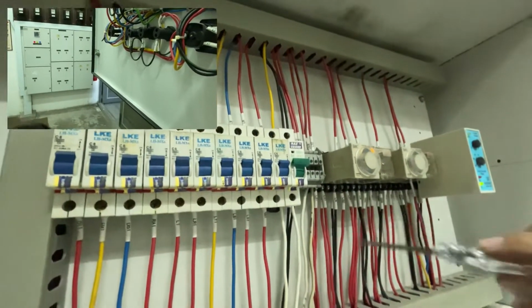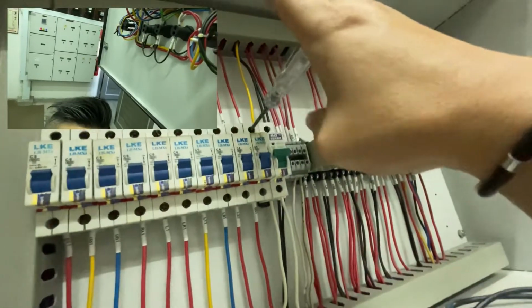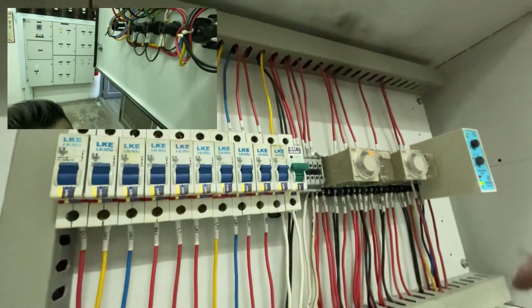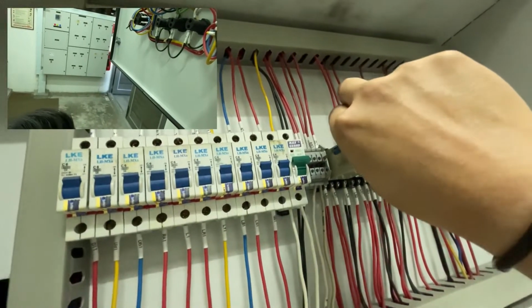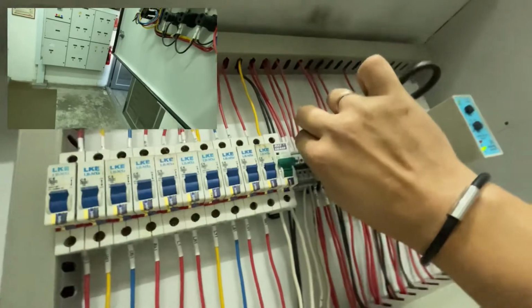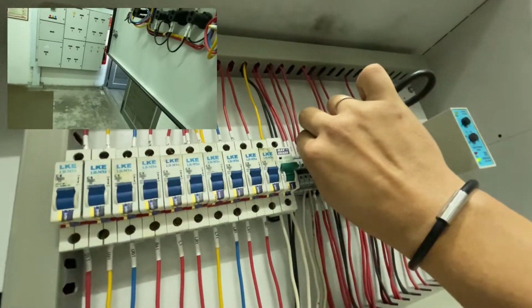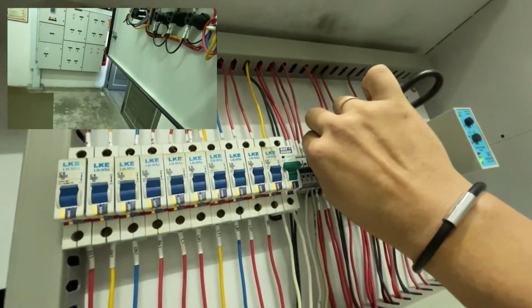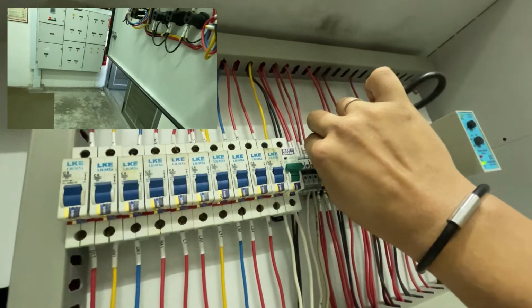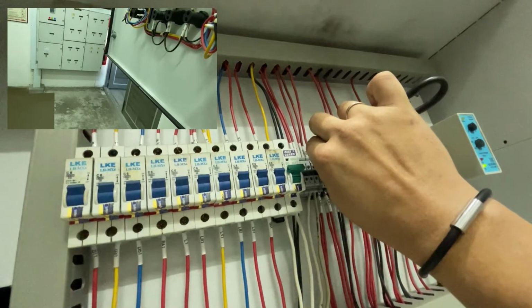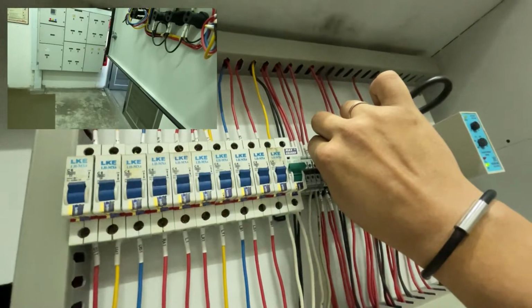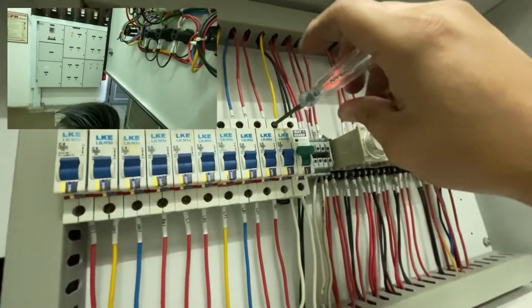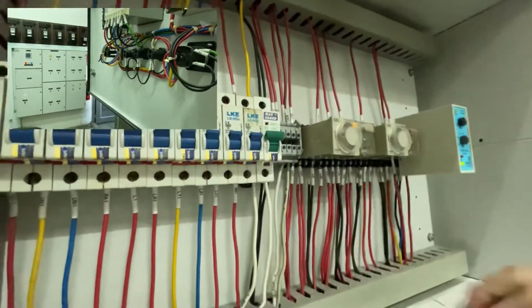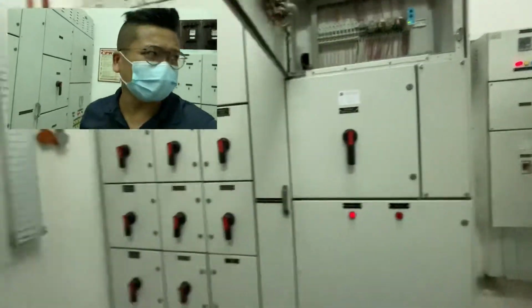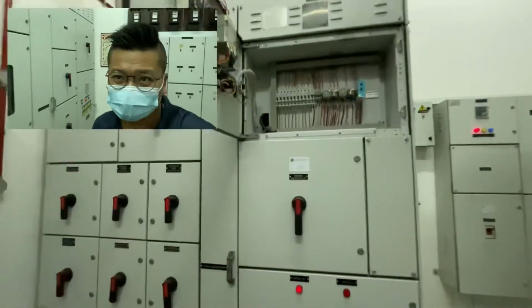The only way to know is to check. Okay, there's no genset supply yet, so I need to try again one more time. This round I need to be really firm to make sure the current can pass through. Okay, this time is running. See, there's genset supply coming. So after about few minutes, the genset will stop by itself.